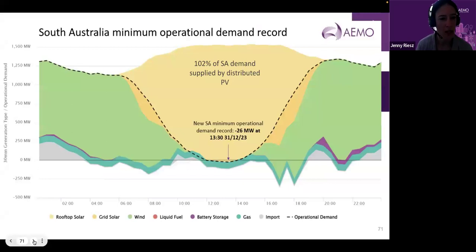This shows the levels of distributed photovoltaics reached in South Australia. Just recently, on New Year's Eve, December 31st, we reached a new record where total net demand in South Australia was negative 26 megawatts—meaning 102% of demand was supplied by distributed photovoltaics, essentially rooftop solar, with 5 kilowatt rooftop systems supplying more than 100% of grid demand. This meant backfeeding from the distribution network to supply industrial loads, including large mines and other industrial customers, up to about 1.2 gigawatts of total demand. It was a historic record and we've learned a lot from looking at this day.